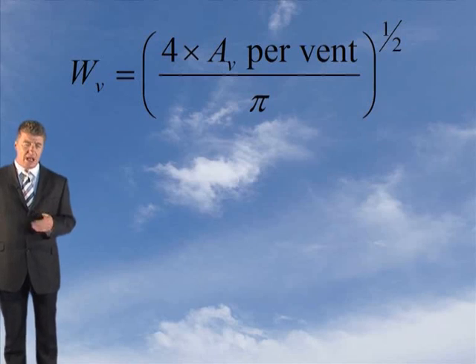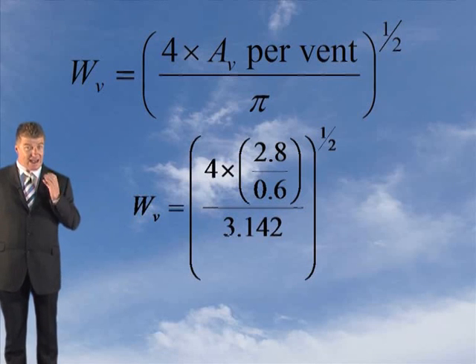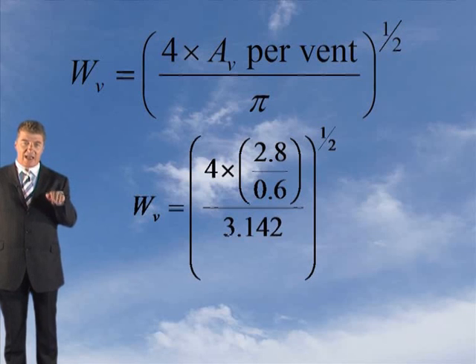When you put this into your formula, your WV formula should have got this. WV equals 4 times 2.8, which is your aerodynamic free area, you need to divide that out by the coefficient to get your geometric free area.